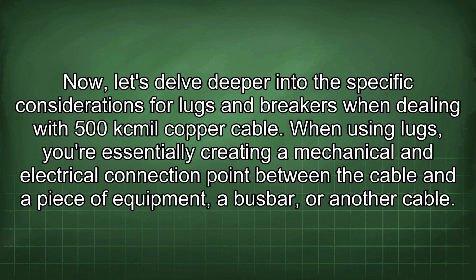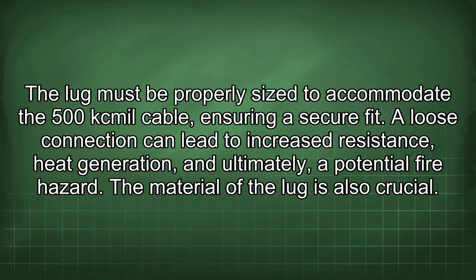Now, let's delve deeper into the specific considerations for lugs and breakers when dealing with 500 kcmil copper cable. When using lugs, you're essentially creating a mechanical and electrical connection point between the cable and a piece of equipment, a busbar, or another cable. The lug must be properly sized to accommodate the 500 kcmil cable, ensuring a secure fit. A loose connection can lead to increased resistance, heat generation, and ultimately, a potential fire hazard.